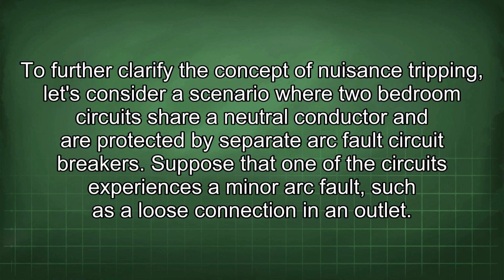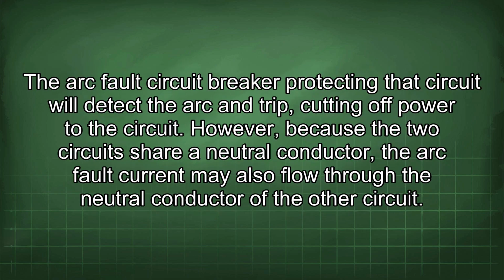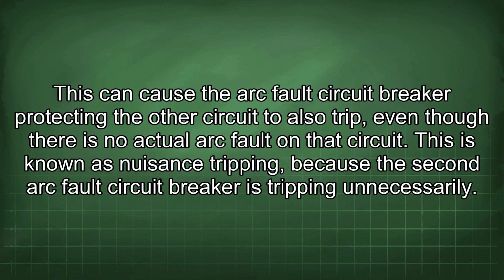To further clarify the concept of nuisance tripping, let's consider a scenario where two bedroom circuits share a neutral conductor and are protected by separate arc fault circuit breakers. Suppose that one of the circuits experiences a minor arc fault, such as a loose connection in an outlet. The arc fault circuit breaker protecting that circuit will detect the arc and trip, cutting off power to the circuit. However, because the two circuits share a neutral conductor, the arc fault current may also flow through the neutral conductor of the other circuit. This can cause the arc fault circuit breaker protecting the other circuit to also trip, even though there is no actual arc fault on that circuit. This is known as nuisance tripping because the second arc fault circuit breaker is tripping unnecessarily.